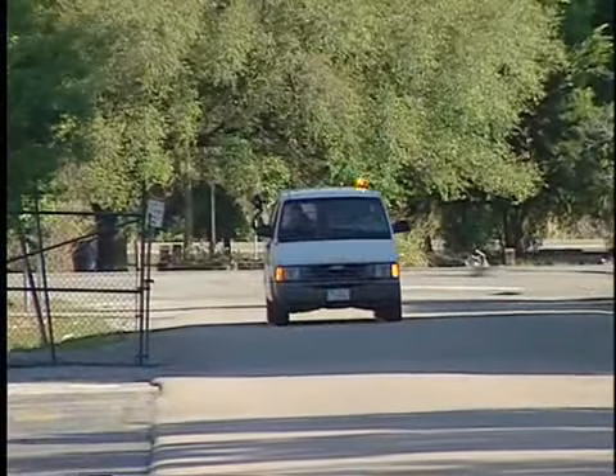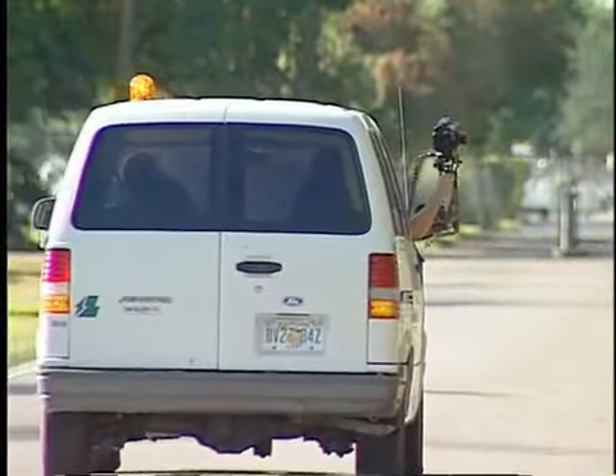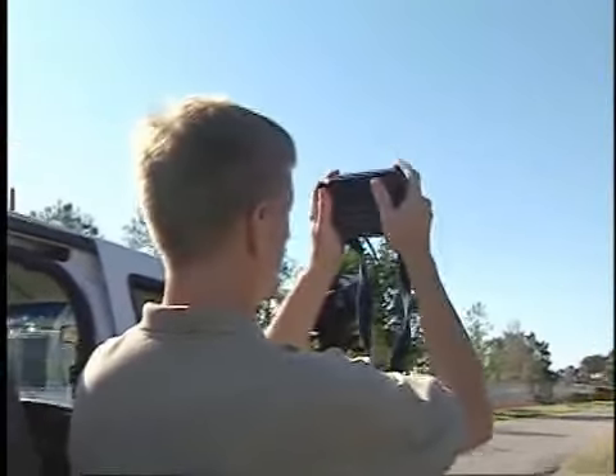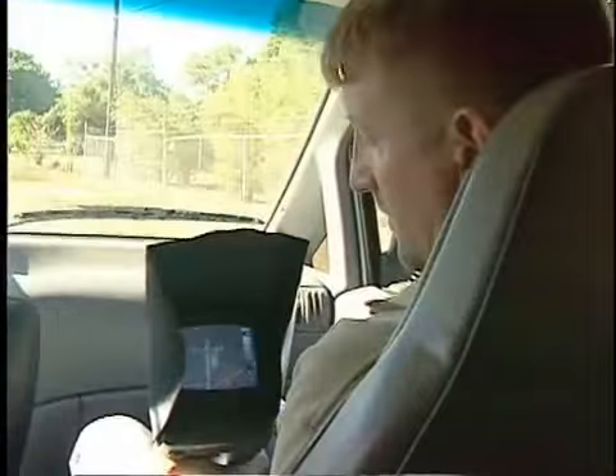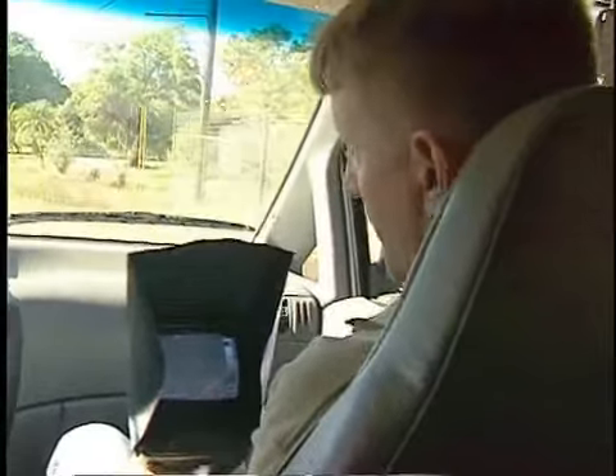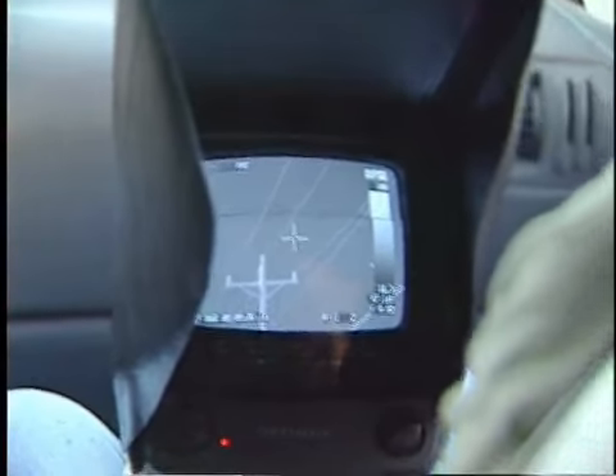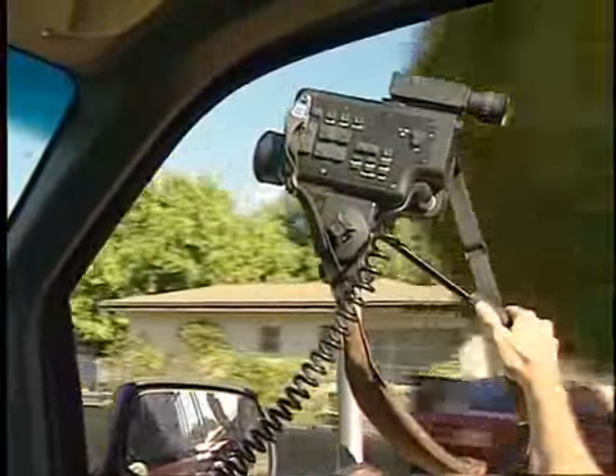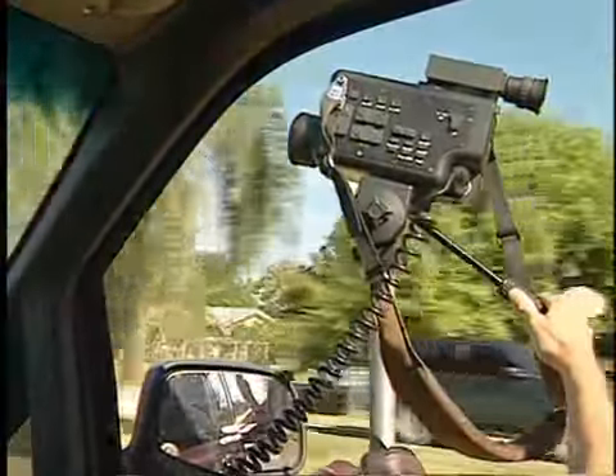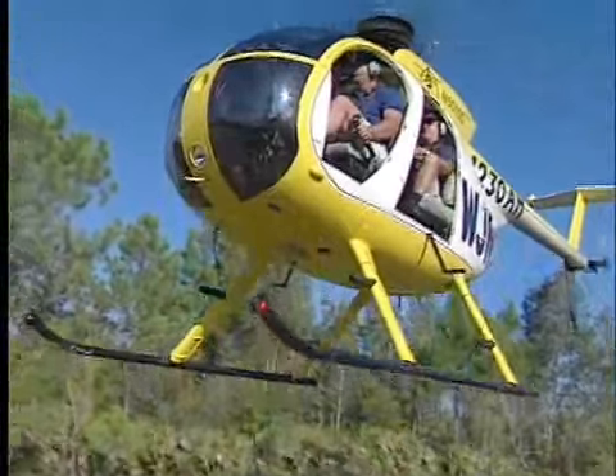Every winter, LCEC conducts a thorough inspection of its substations and lines by taking real-time photos of the equipment with an infrared camera. The inspections are performed during the winter because the contrast between the cooler temperature in the environment and the heat emitted from the equipment allows for a more accurate detection of problem areas. Many times, these inspections are performed by helicopter, a more efficient way of reaching wires and poles not accessible by ground.